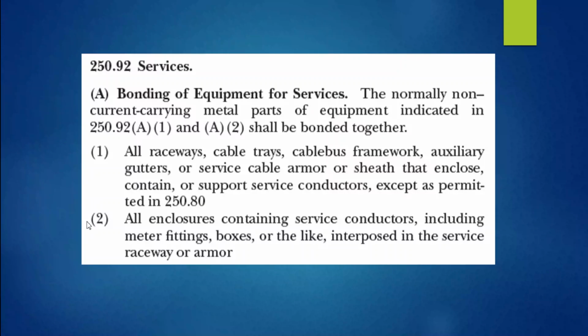Number 2 says all enclosures containing service conductors, including meter fittings, I guess that would also be meter enclosures, boxes, or the like, that are interposed. That means it's been put in place in the system between the service equipment and the utility. Generally you're only going to deal with the portion from the service point toward the premises wiring. But if anything is interposed in that system and it is metal, like a meter disconnect, a meter enclosure, or a CT cabinet, all of that type of stuff that's going to be interposed in the service raceway or armor at some point, all of that has to be bonded together.